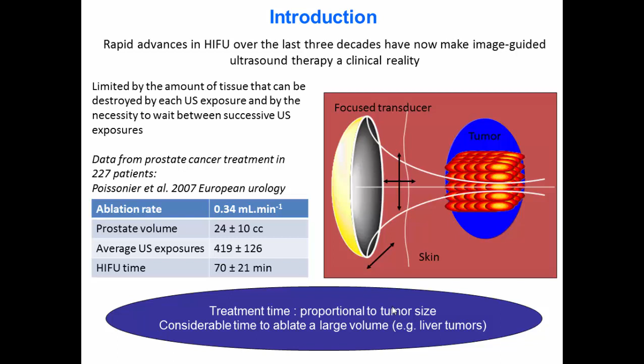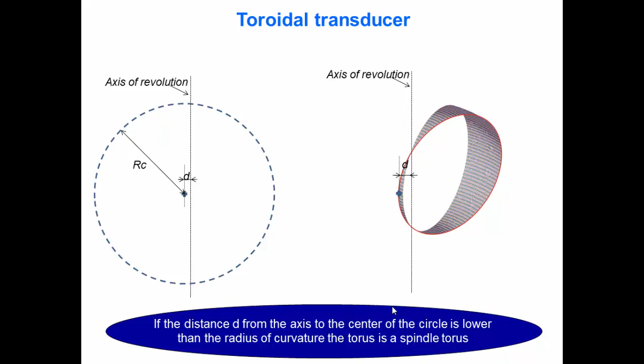So for treating the liver, we changed the shape of the transducer, and rather than using spherical transducers, we used a toroidal transducer. So what is the difference between a spherical and a toroidal transducer? The difference is that a torus is based on the rotation of a circle about an axis of revolution. But the difference with the spherical one is that the center of the circle is placed at a distance d from the axis of revolution. And when the circle rotates, it creates a torus.